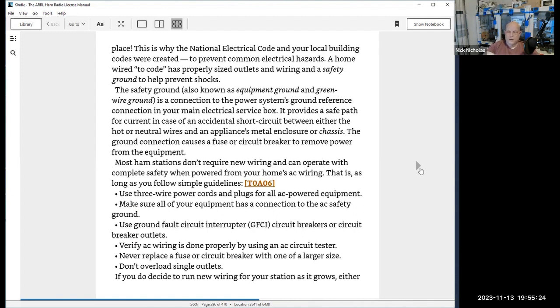Another thing I'm going to quickly tell you about safety is if you ever hook up a home generator to your house temporarily, disconnect the load, the main connection to the power coming in. If the power's out, you hook up your generator and you leave it all connected, there are 2 terrible things that can happen. One, you feed 110 volts back down that line. It goes through the transformer and becomes 13.8. And now the guys working on the line that's supposed to be turned off get electrocuted.